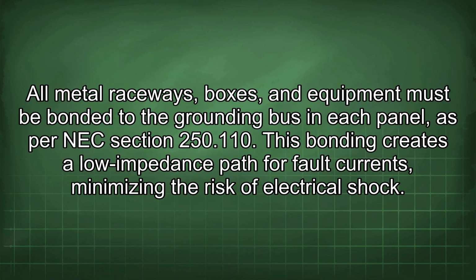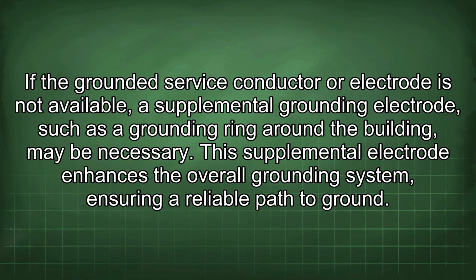All metal raceways, boxes, and equipment must be bonded to the grounding bus in each panel, as per NEC section 250.110. This bonding creates a low impedance path for fault currents, minimizing the risk of electrical shock. If the grounded service conductor or electrode is not available, a supplemental grounding electrode, such as a grounding ring around the building, may be necessary. This supplemental electrode enhances the overall grounding system, ensuring a reliable path to ground.